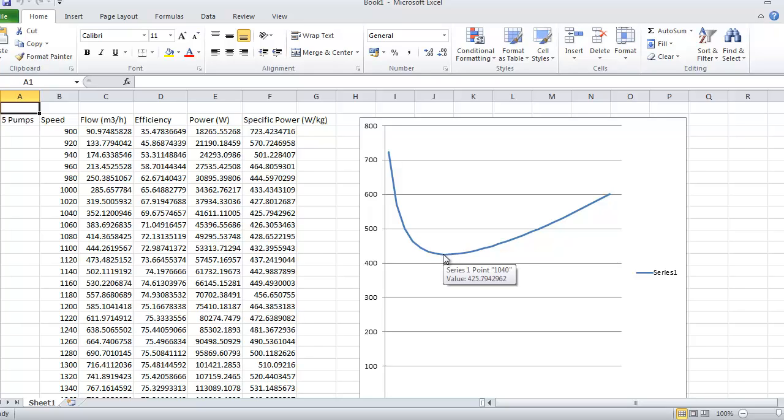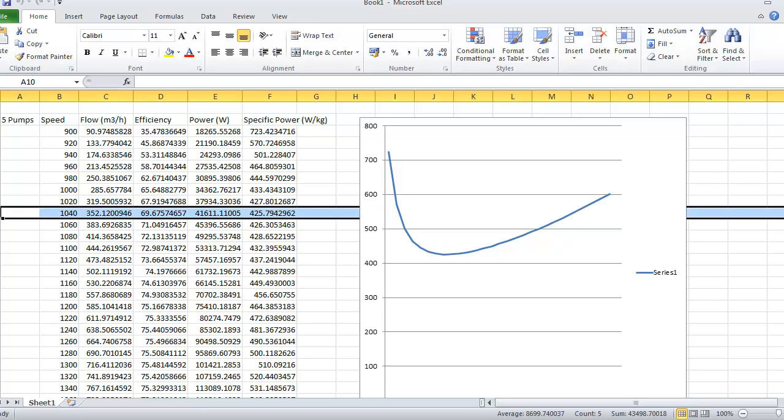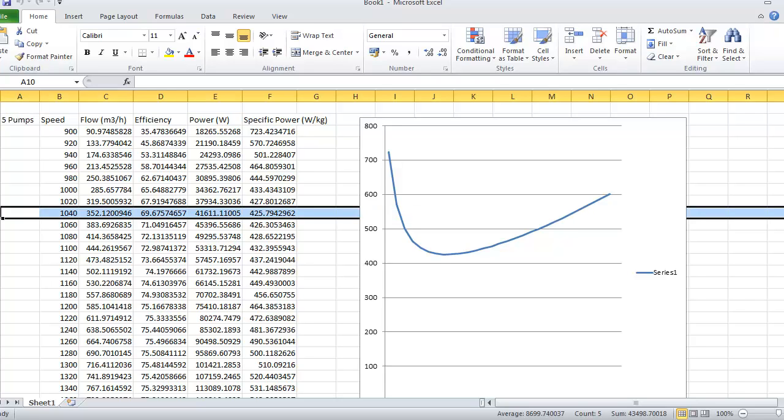If we leave the cursor on the graph, it reveals that the most efficient operating speed is approximately 1040 RPM. A quick look at the table of results should confirm this. As we can see, 425 watts per kilogram represents the lowest specific power requirement.